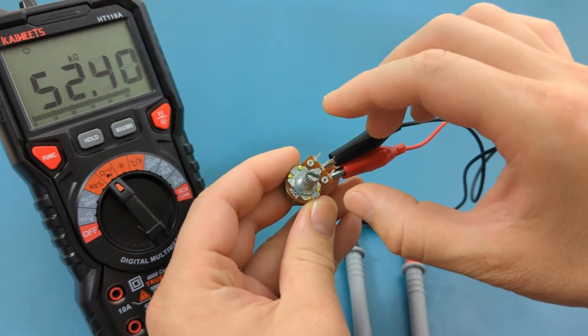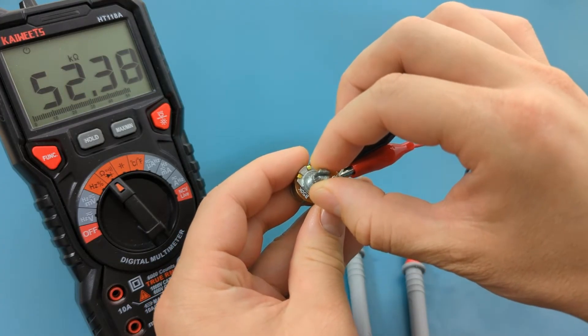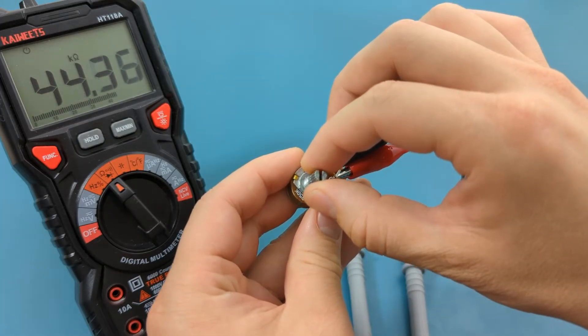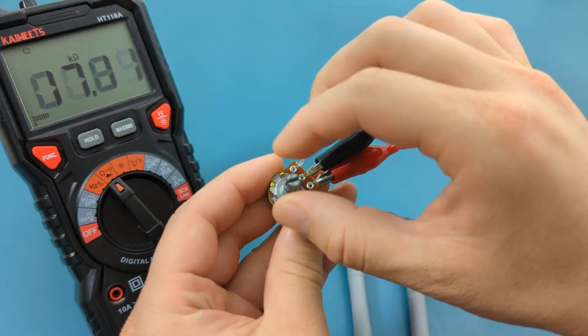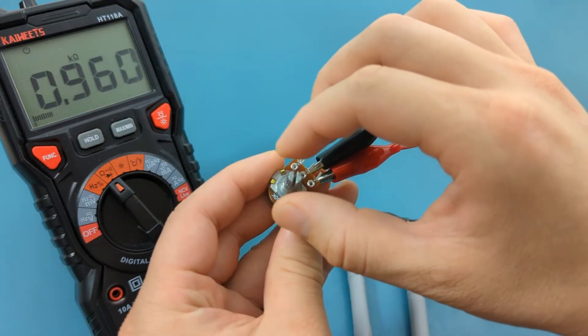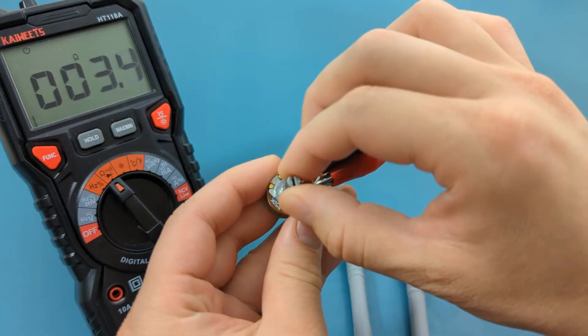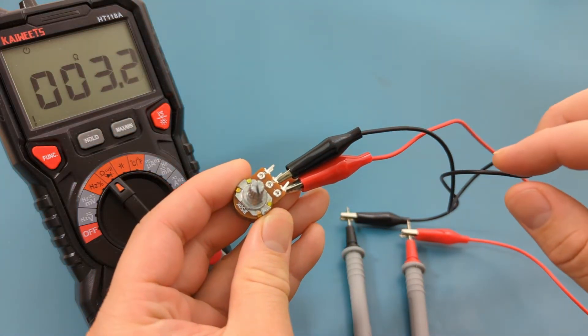The maximum resistance is around 52 kilohms. When you turn the dial counterclockwise, the value of the resistance decreases. The transition of the resistance should be smooth as you move the dial clockwise or counterclockwise. The minimum resistance is around 3 ohms.